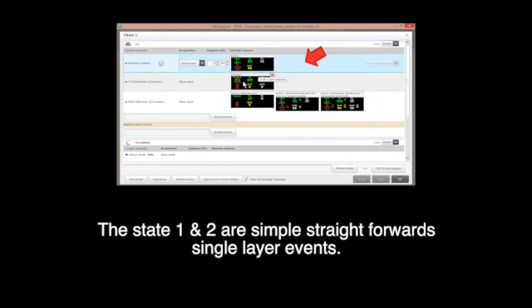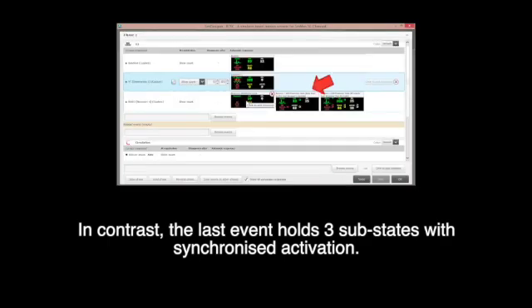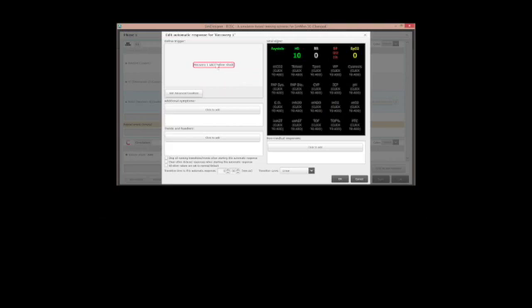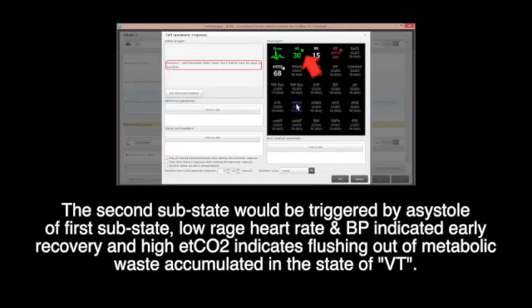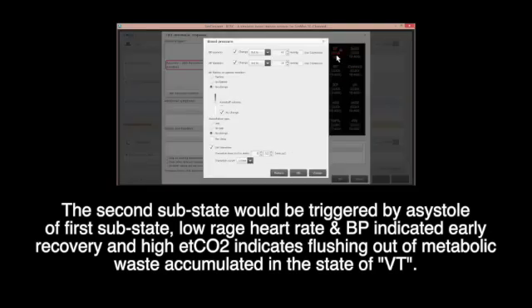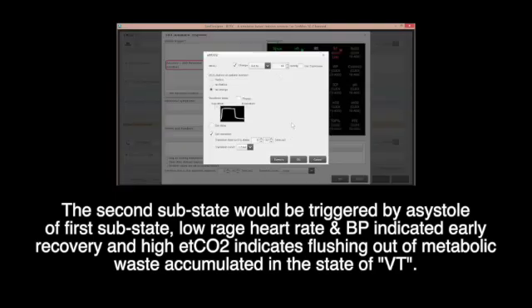Overview of programmed ROSC: states 1 and 2 are simple, straightforward, single-layer events. In contrast, the last event holds three substates with synchronized activation. This coordinated manipulation begins with a click on ROSC and defibrillation detected by the system. The first substate gives commands of post-defibrillation ECG flatline with low parameters to allow subsequent regain of each parameter. The second substate is triggered by the asystole of the first substate — low range heart rate and BP indicate early recovery, and high ETCO2 indicates a flushing out of metabolic waste accumulated in the state of VT.